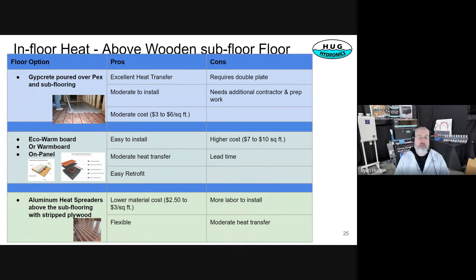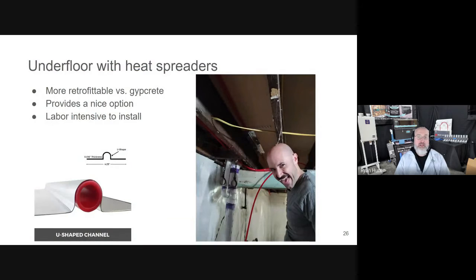Ranked in our favorite options, the gypcrete, like I explained, moderate price, moderate to install, high performance. The Eco-Warm panels and above floor board type systems are more expensive, pretty easy to install. And the aluminum heat spreaders are much more work, but they're less expensive per square foot. So underfloor with the heat spreaders is another option. It's very popular because it's out of the way and doesn't affect your subfloor, your floor heights, or anything like that.